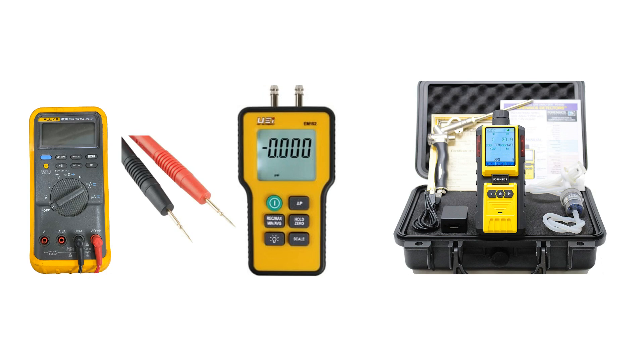If you are receiving an EA error code, there is no flame detected. To troubleshoot, you will need a multimeter, test leads, a gas manometer, and a combustion analyzer.